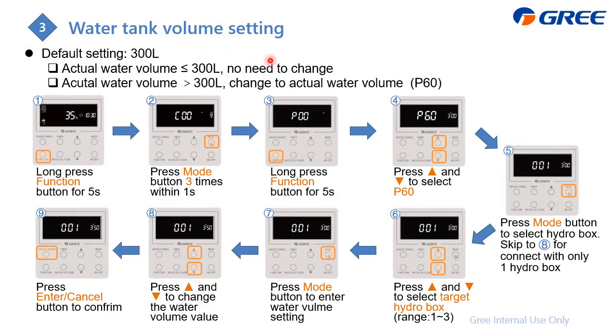Water tank volume setting. The purpose of this one is just to tell the system the capacity or the size of the water tank. If it is less than 300 liters, no need to change it. If higher than that, you need to change to the actual water volume. Just follow these steps and you can change the volume. The first is to get into this P60 to change it. And as this one wire controller controls the mounted hydro box, first just find out your target hydro box, which is connected to the water tank, and then change to the actual volume. It's okay.